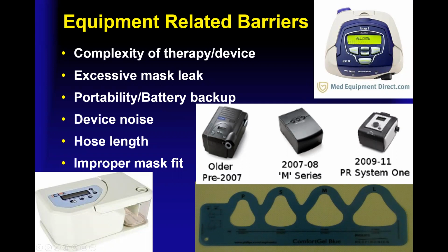So your newer CPAPs are auto-titrating, where within a range, they'll go up and down depending upon the patient's position or weight loss or weight gain, things along those lines. You now have ramp features. Well, we had that 30 years ago, but the ramps are better, where it starts at a lower pressure, lower flow, more tolerable. Hopefully the patient falls asleep, and then it picks up to the desired level.